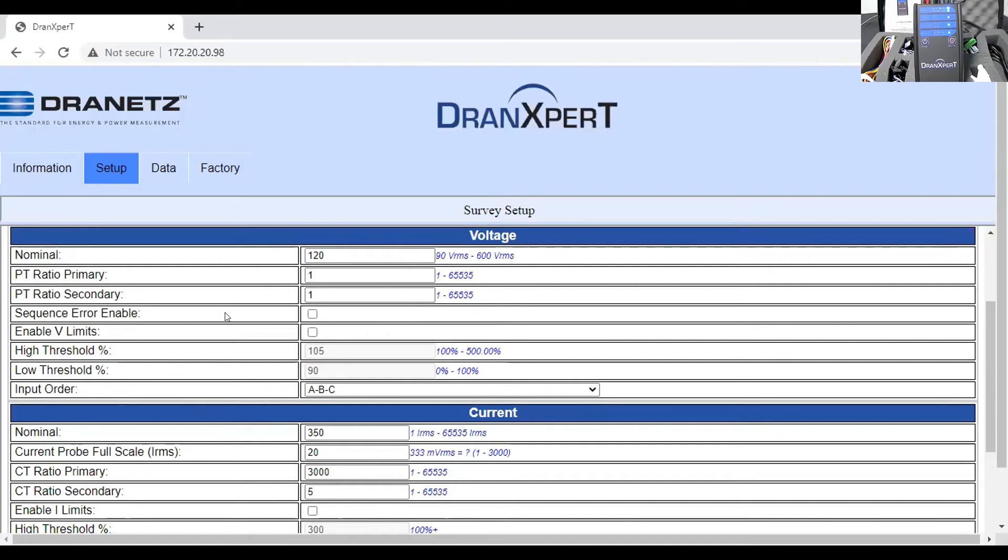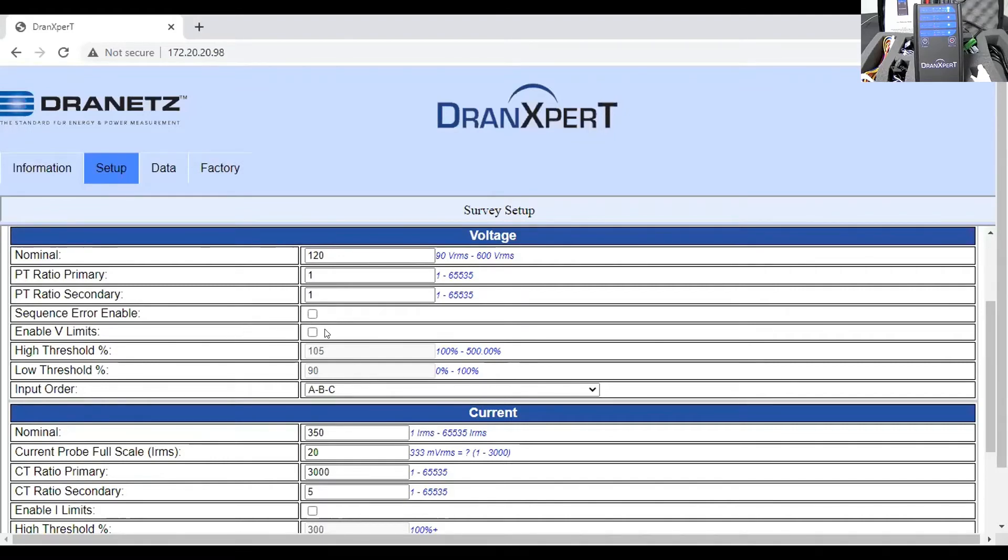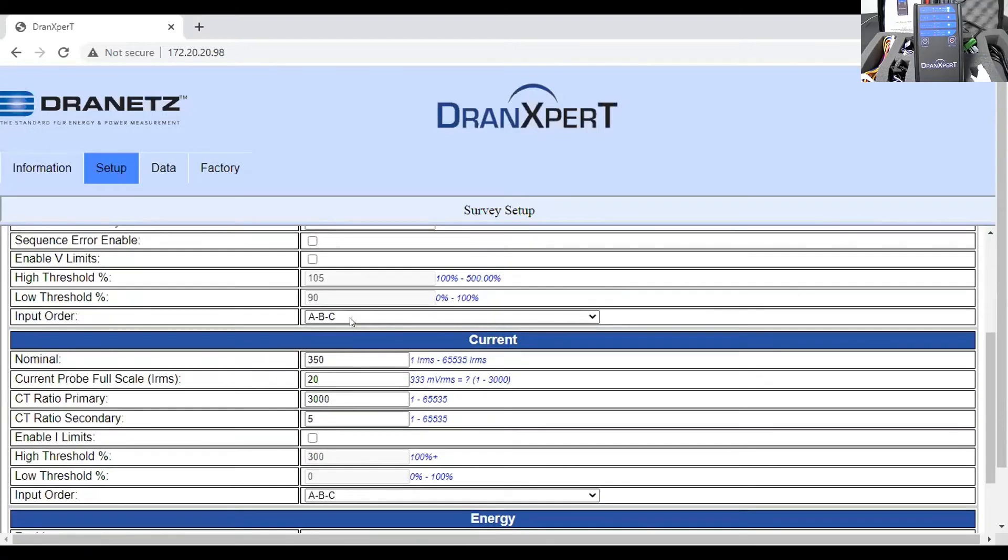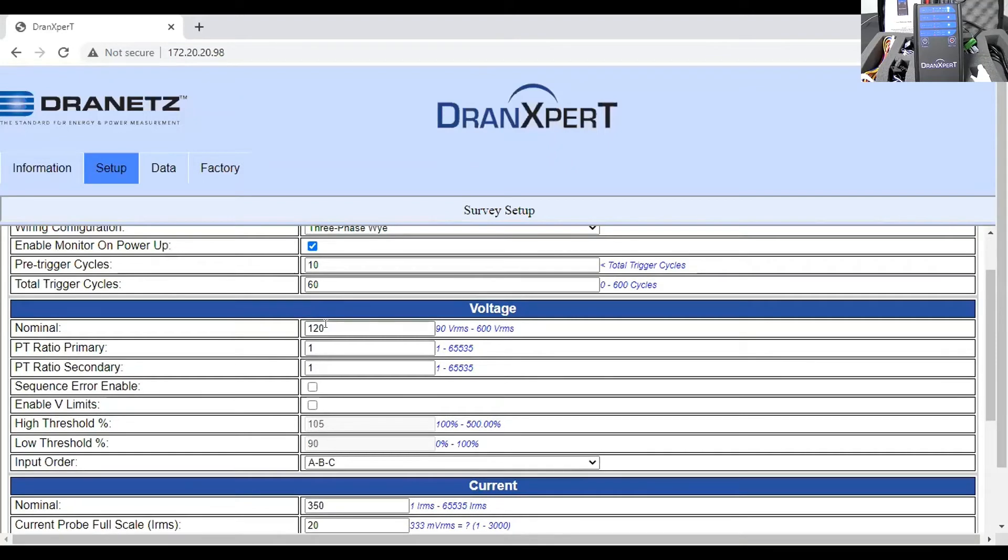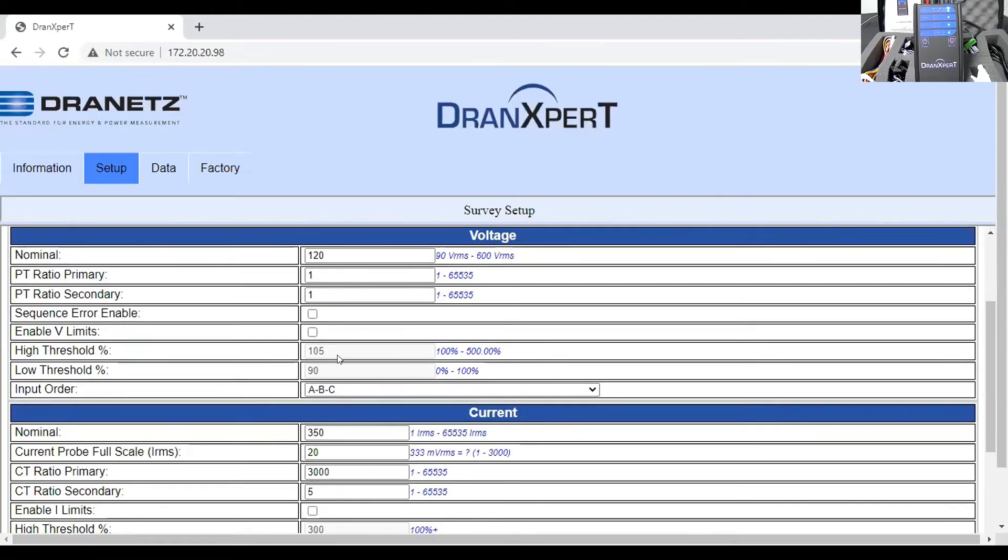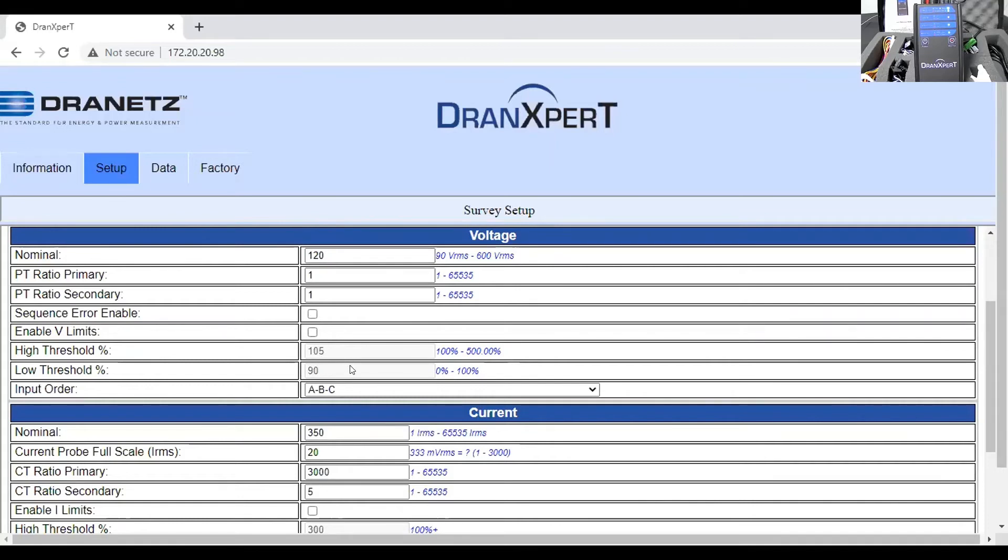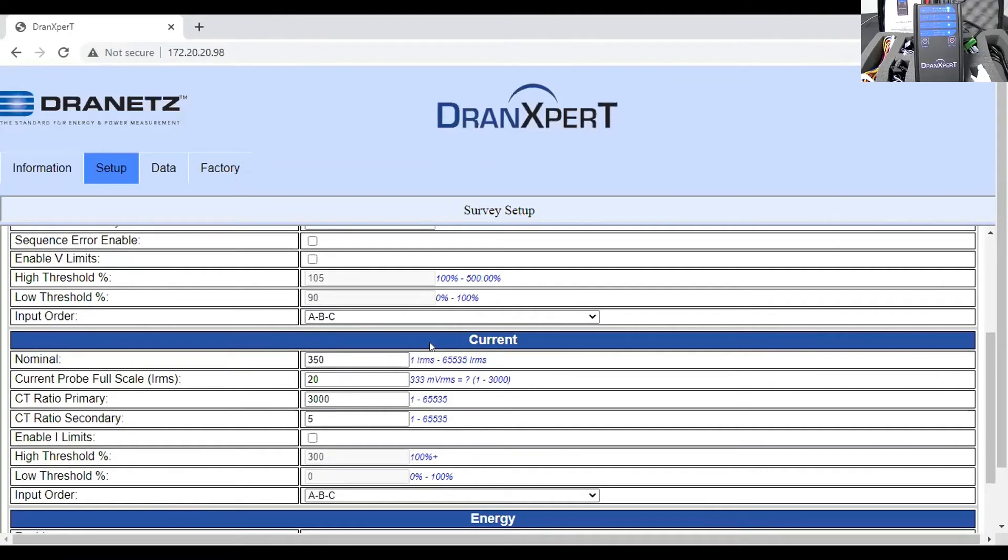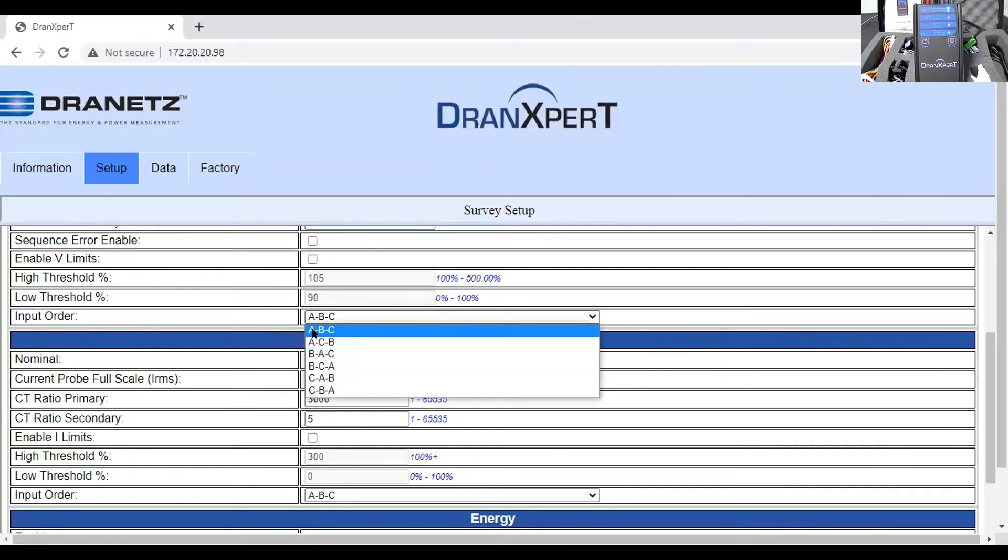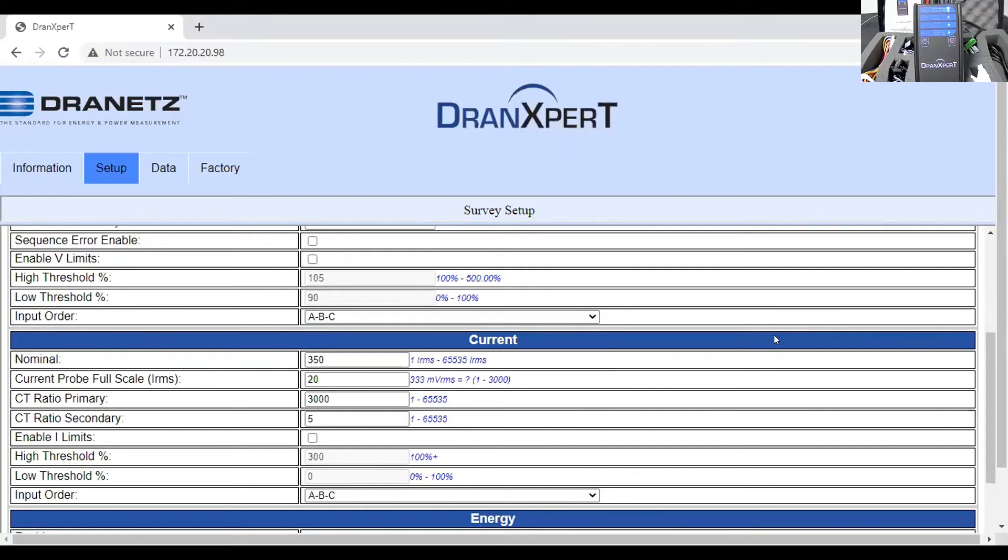Sequence error enabled, this allows you, your typical, what we call reverse sequence, you can have the instrument actually detect when it's just the opposite of that. Enabling limits, so this turns on fault recording, if you will. And it's about just simply setting a percent of your nominal, uses the, in this case here, nominal 120. And then our trigger limits is 105. So you can think of this in terms as 5% above 120. That's our upper limit. And then at 90%, 10% below 120 is our lower limit. So now we've defined our window. Anything that goes outside that window, an RMS variation, of course we use half-cycle resolution, it goes outside that window, it's detected as a fault. We can change our input order. So there's options here of changing the input order. Typically it's going to be an ABC, but in some cases you may want to change that. So you can see it's pretty versatile in that regard.